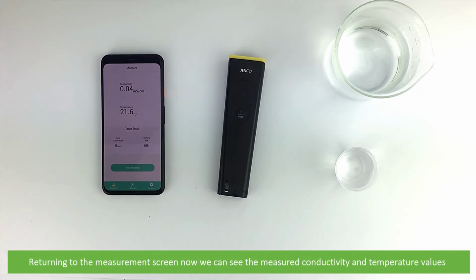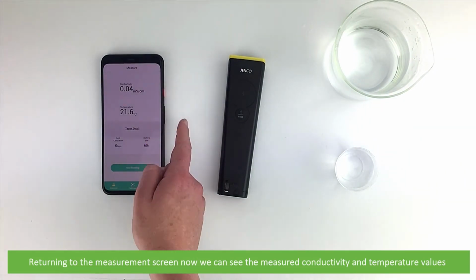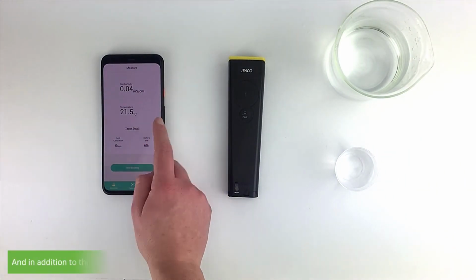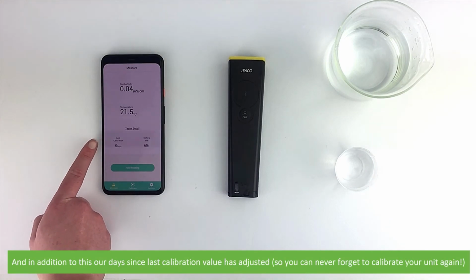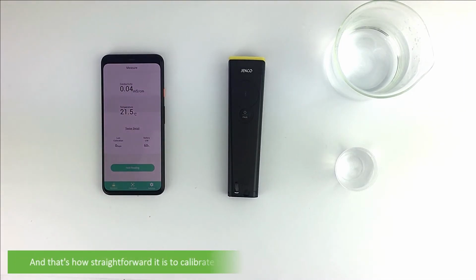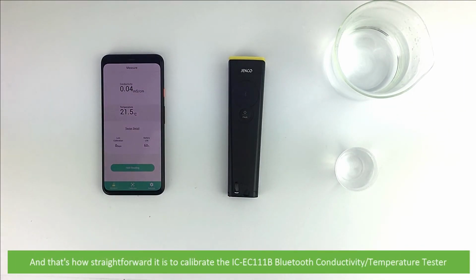Returning to the measurement screen now, we can see the measured conductivity and temperature values. In addition to this, our days since last calibration value has adjusted, so you can never forget to calibrate again. And that's how straightforward it is to calibrate the IC-EC111B Bluetooth Conductivity and Temperature Tester.